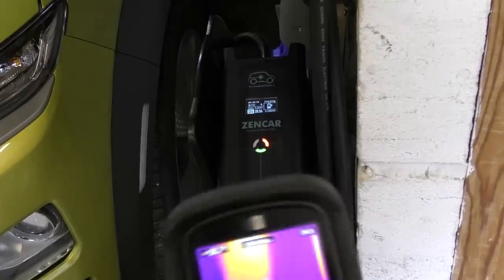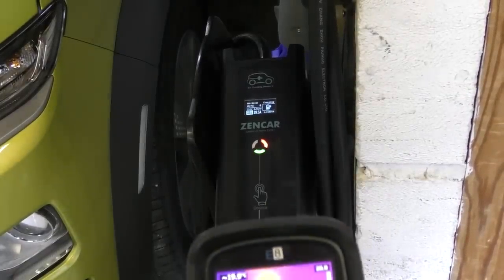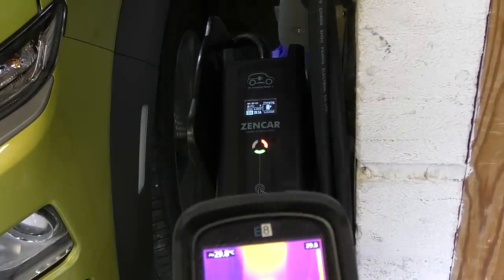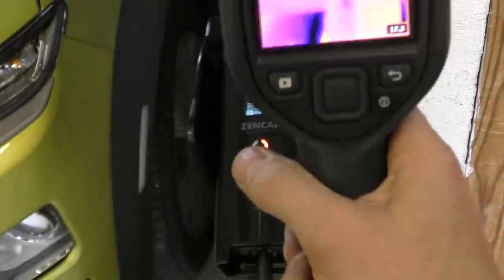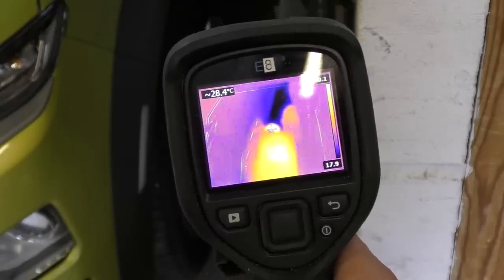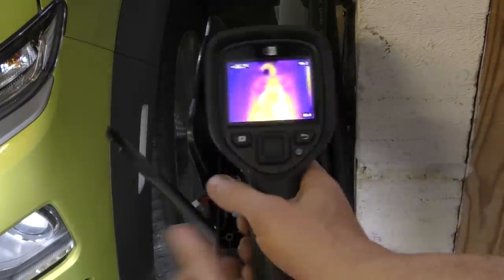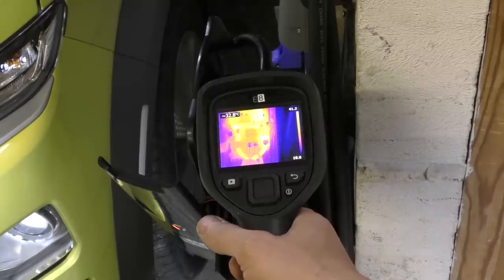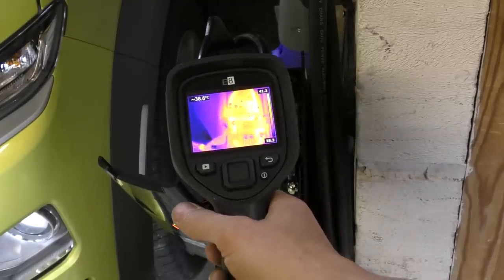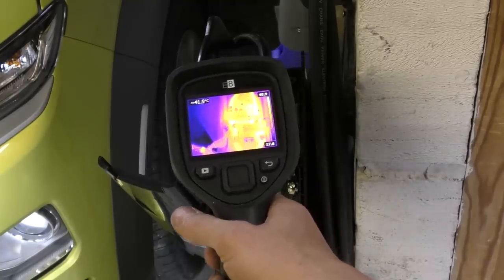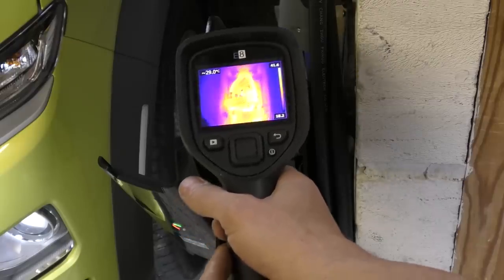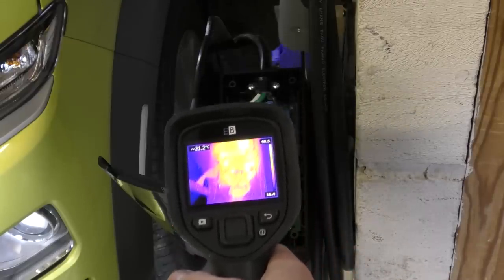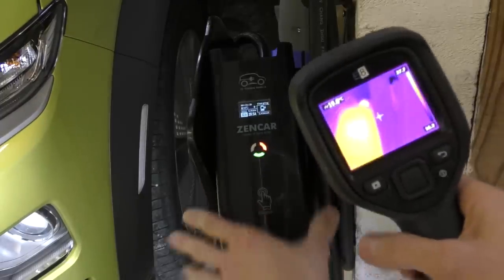So temperatures on this one, it's been running for about half an hour. Again, we've got about 29 degrees on the output cable, about the same, 31, on the input cable, and inside we've got nothing over 40 degrees, 41 at the bottom of that relay. So yeah, all perfectly fine temperature wise. Reading 36 on the internal display.